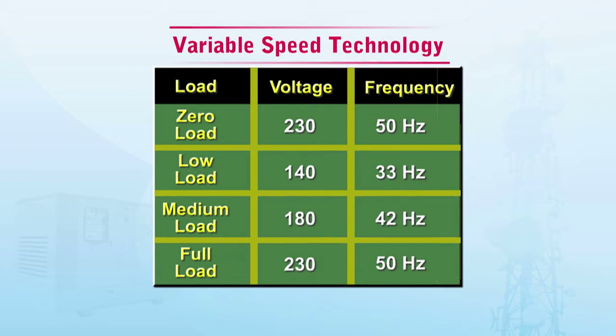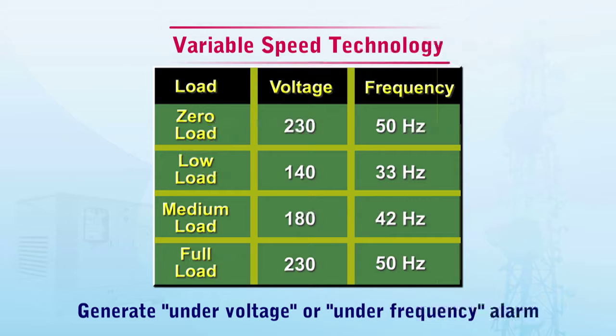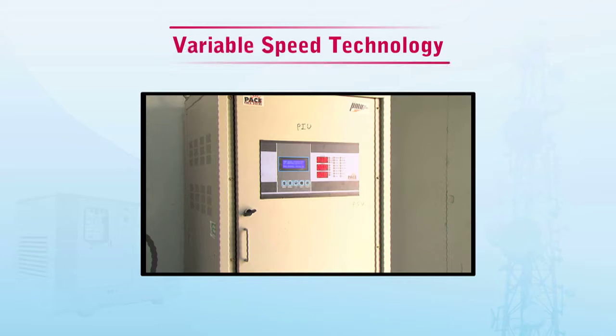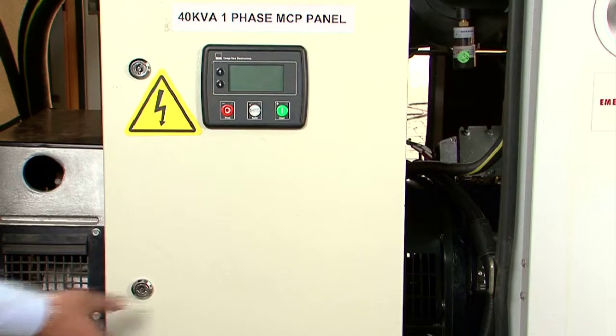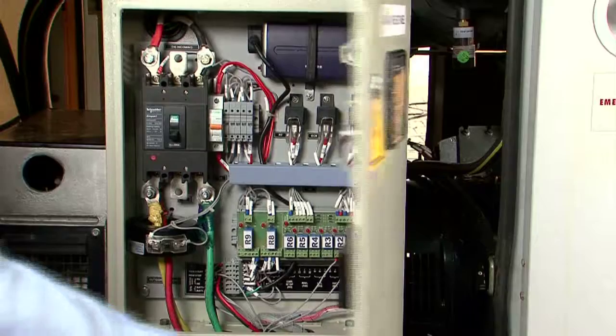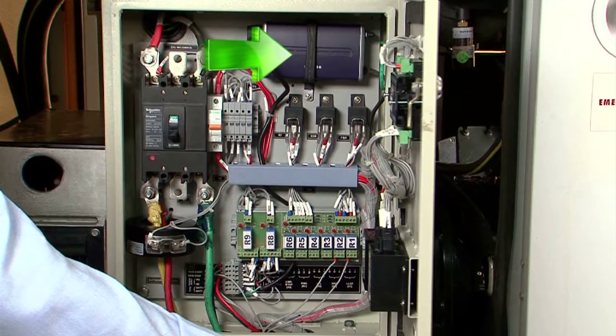Special features of the new variable speed genset. As we have just seen, the new variable speed genset develops variable output voltage from 140 to 230 volt at variable frequencies from 33 to 50 Hz. However, such variable speed operation can sometimes generate under voltage or under frequency alarms in the PIU's control card. As a result, the PIU can send an unwanted remote stop command to the genset whenever it operates in the variable speed mode. To overcome this situation, the new control panel contains a special DC to AC inverter.